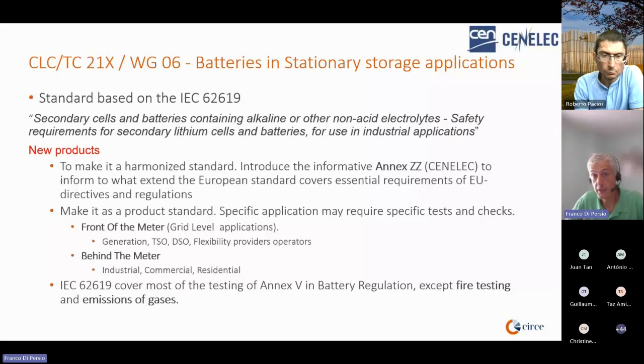Specific applications may require specific tests and checks. Front of the meter will be one situation. Behind the meter, for industrial, commercial and residential applications, can also require specific tests. So the basis would be IEC 62619, but then things need to be adapted, also considering that some tests foreseen in the battery regulation are not included in this standard, for example fire testing or emission of gases. So there is work going on on those aspects.